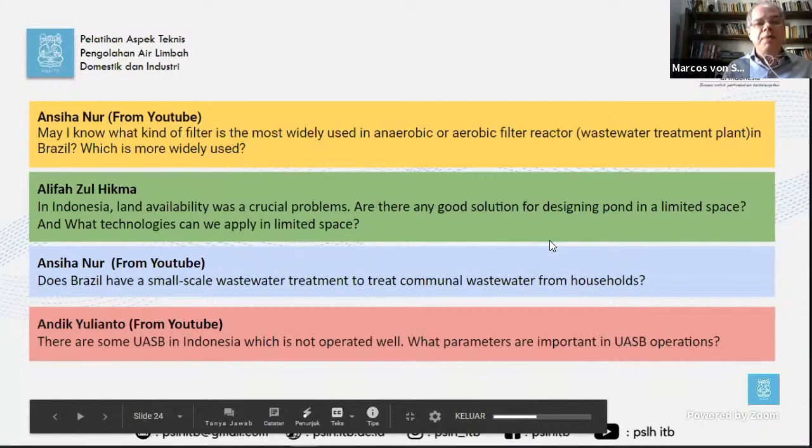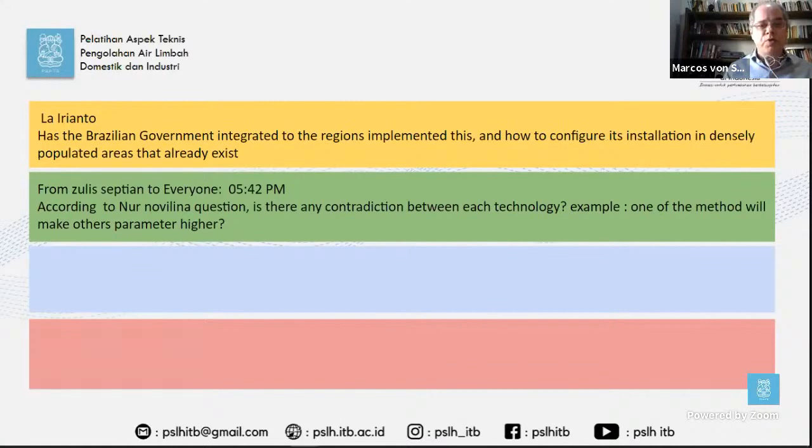The question of odor, which is very important. There are some means in which you can collect your biogas and you can treat the biogas in order to remove the odors. Corrosion is also a problem. Above the liquid level, you can have corrosion in the upper part of your reactor. Now, with lots of research, you can use construction materials that are more resistant. You can use stainless steel, of course, it's very expensive. Steel with a protective coating can be good.